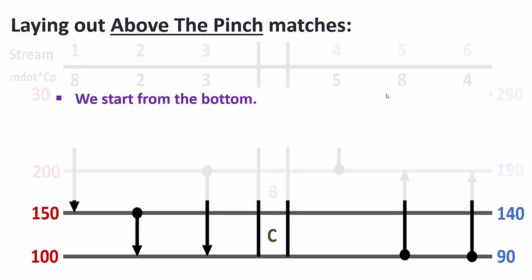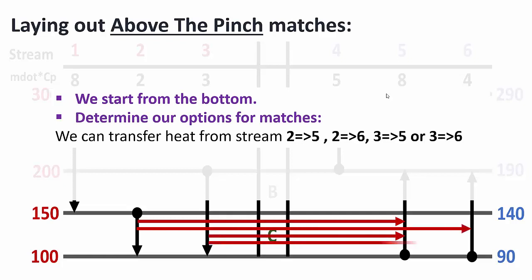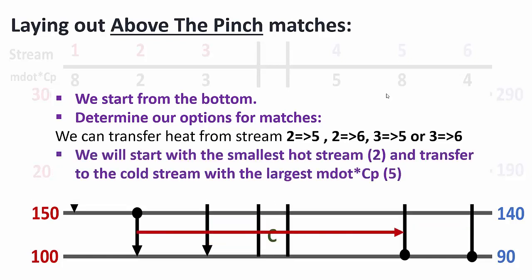We always start from the bottom when working on heat exchanger design above the pinch. We determine our options for matches first. Working horizontally, we can match streams 2 and 5, 2 and 6, 3 and 5, or 3 and 6. But we start with the smallest hot stream, which is stream 2 — it has the lowest Q — and we transfer this to the cold stream with the largest M_dot·Cp, which is stream 5. So our first match is between streams 2 and 5.